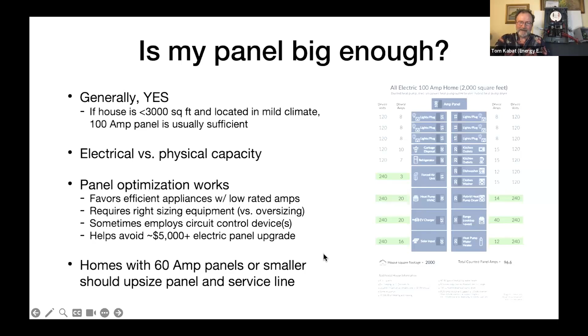And this panel optimization works. It's helping people save $5,000 to $30,000. The small numbers when you've got overhead lines, and it wouldn't cost that much to upsize your electric panel. Maybe $3,000 to $5,000. And the higher numbers are when you've got underground trenching that has to happen to make a bigger service wire. That's what they call the wire coming to your house. But homes with 60 amp panels, we're finding are generally those panels are a bit small for our opulent lifestyles here in the Bay Area. So we tend to recommend upsizing to 100 amps or bigger for those.